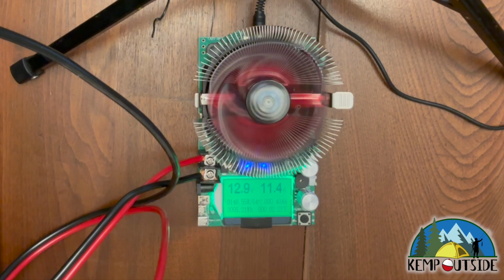So what we're going to do is just let this run until it shuts off, because once the BMS says you've taken everything out you can, this will shut itself down, the timer will stop, and it'll give me the amp hour capacity of the battery. Pretty simple. I'm going to let it run and come back when it's done.